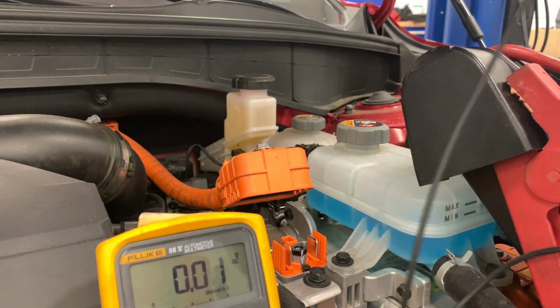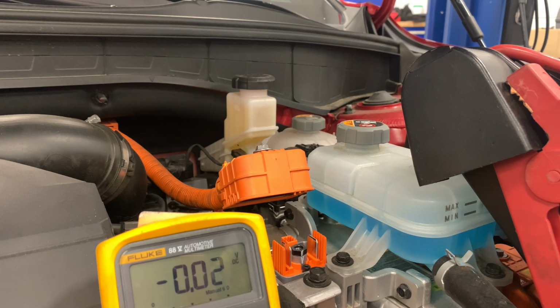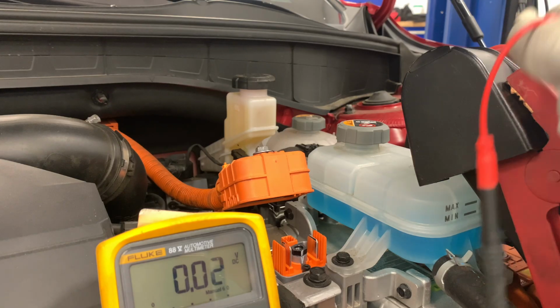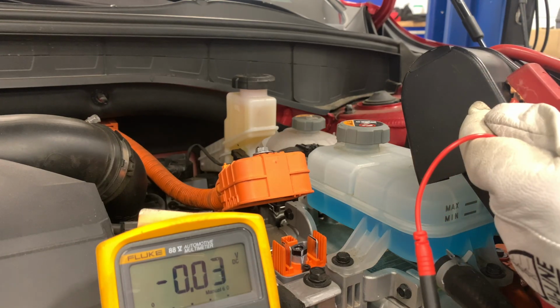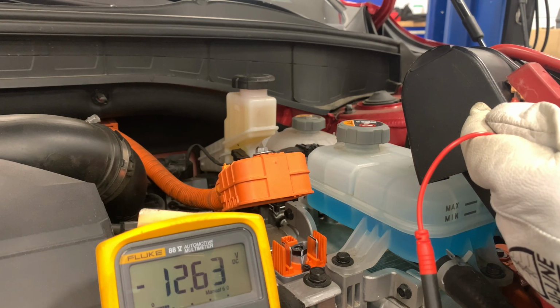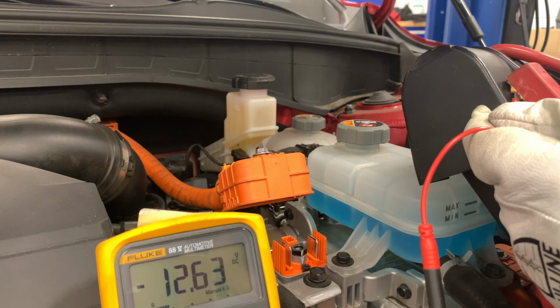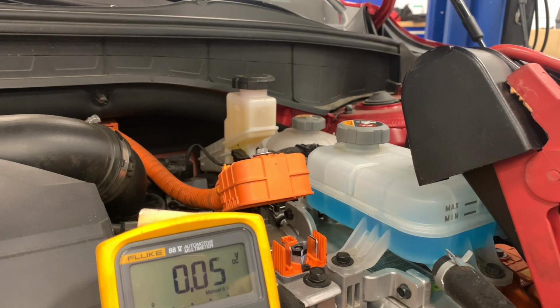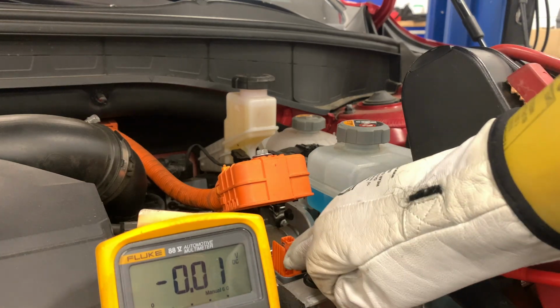So we know the capacitors inside the inverter have drained. Now, to make sure our meter was correctly reading 0 volts, we're going to go back to the jump box. 12.63 volts, perfect — that's what we want to see. So we know nothing bad happened to the meter while we were measuring, and that it legitimately has only 0 volts here.